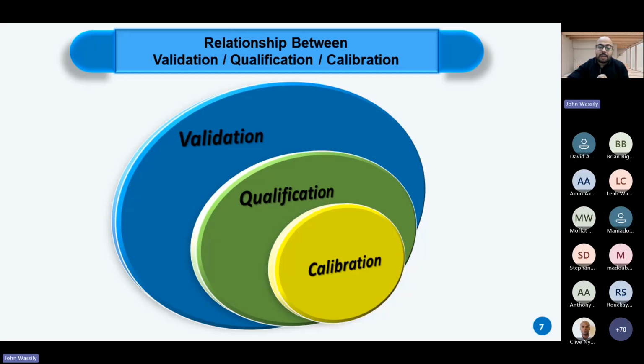For example, I cannot rely on a sterilizer autoclave before making sure that its critical sensors, like temperature sensors, are calibrated. Then I can go for its qualification to make sure it will consistently produce a product that is sterile and free from any microorganism. Finally, I can use this qualified sterilizer autoclave in the manufacturing process. By performing process validation, I have a validated process that used qualified equipment, and that equipment was calibrated for its critical sensors. This is how the interaction and relationship between these terms occurs.